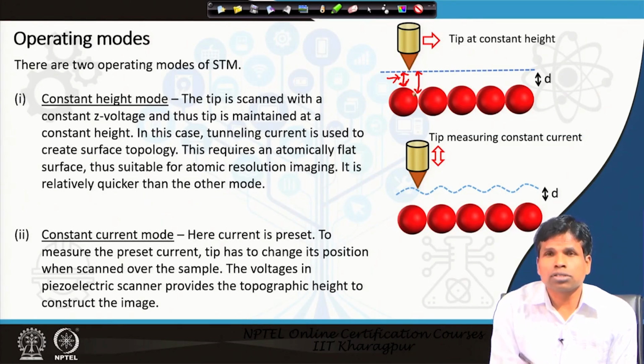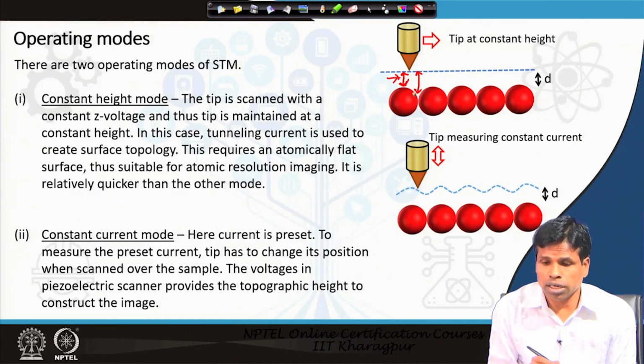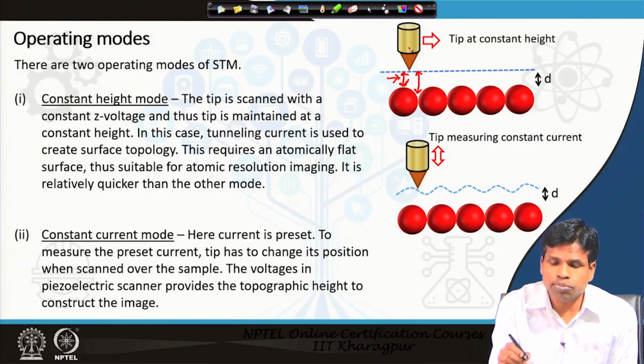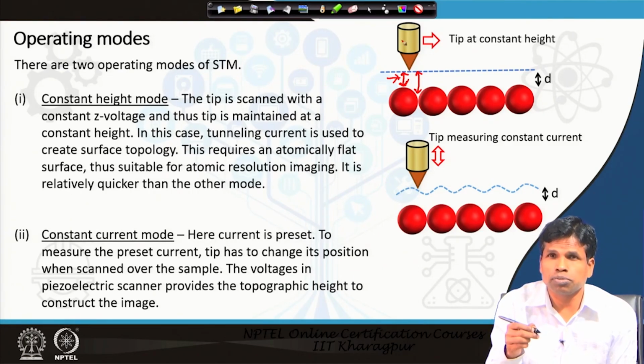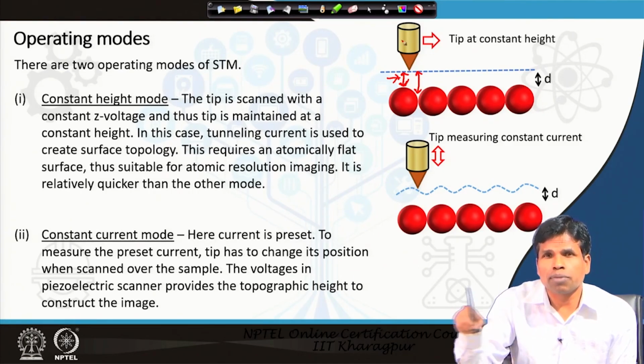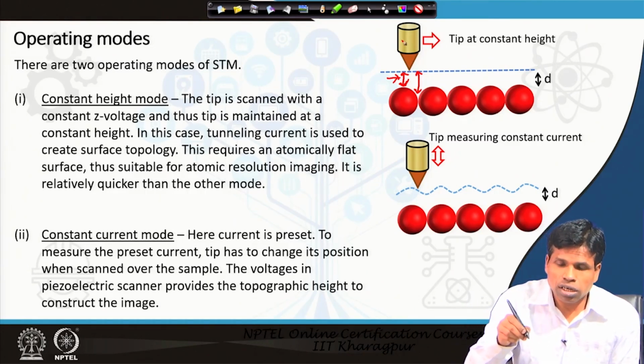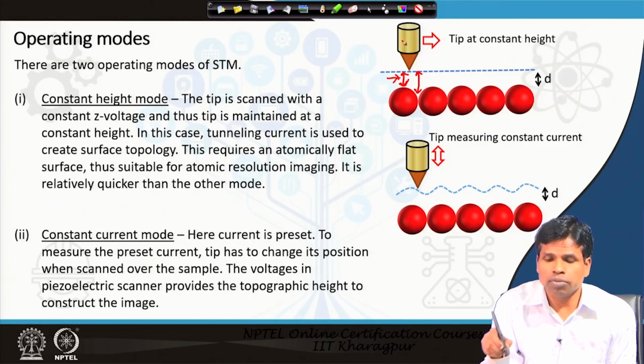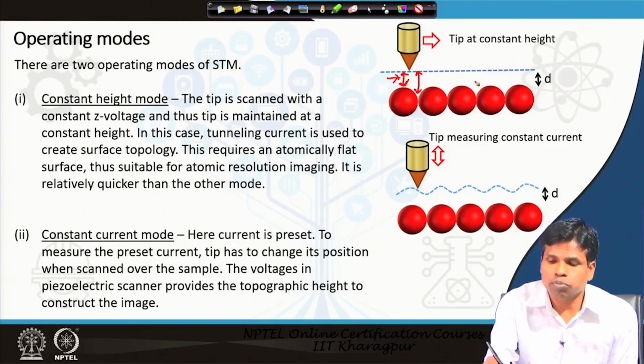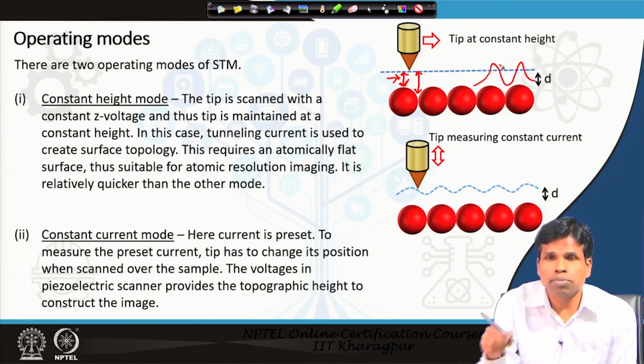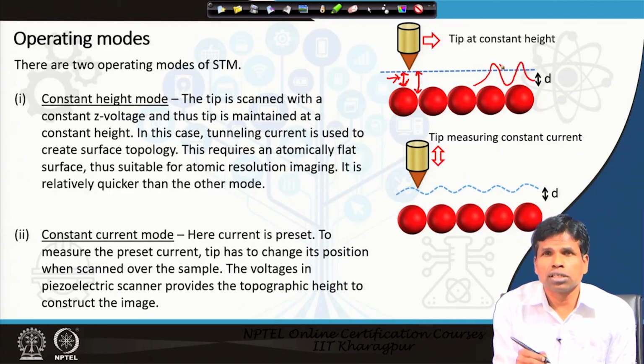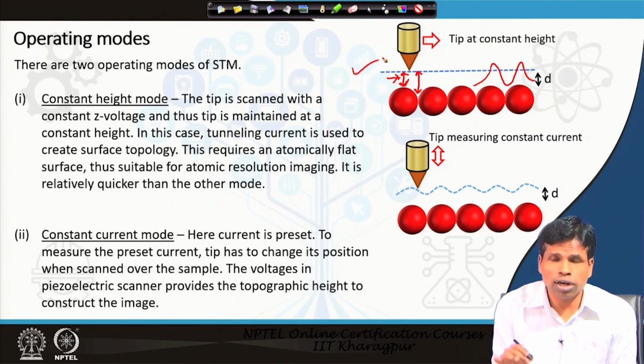So, we get the surface topology from the current data, or tunneling current data, in this case, and moreover this is a fast way of doing it, because we do not change the voltage to the piezo scanner. As we do not change the voltage to the piezo scanner, the tip can move at a faster rate. So it is an advantage that we can do scanning very quickly, but it also has a disadvantage: if the sample is very rough, then the tip may crash. Once the tip crashes, artifacts will be generated, the tip shape will be distorted and artifacts will form. So, this type of study can be done for an atomically smooth sample. If we know already that the sample is very smooth, then we can use this mode.